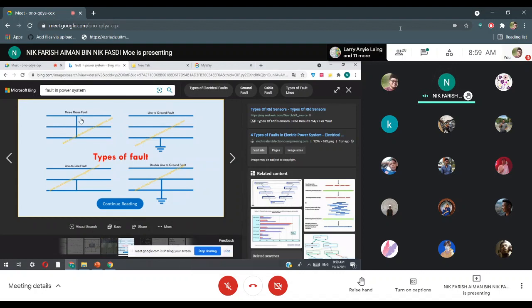That's why you kena kira per unit system. Different impedance, dari situ you akan tahu berapa fault current. From the fault current, the size of fault current, barulah you boleh decide the size of relay yang nak pakai, berapa besar relay, protection relay, protection device yang you nak guna untuk protect you punya network.